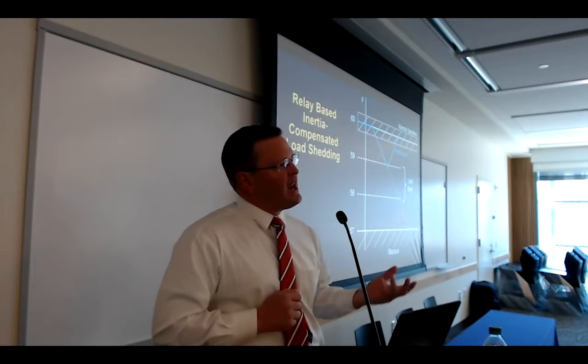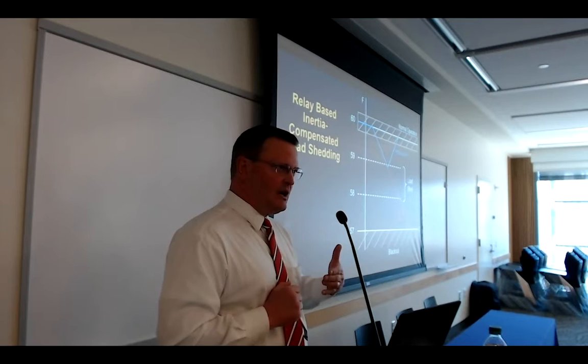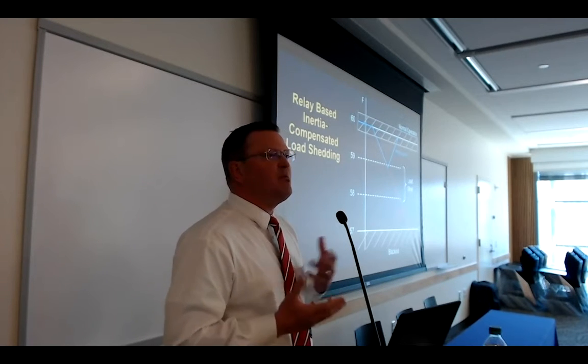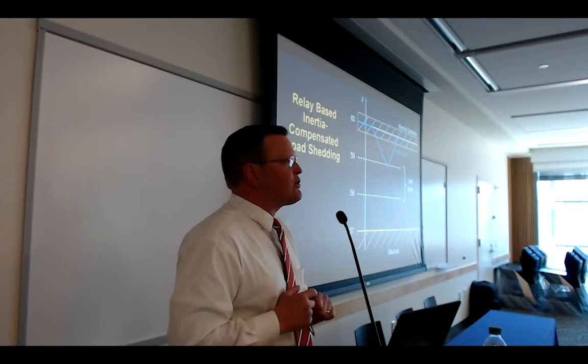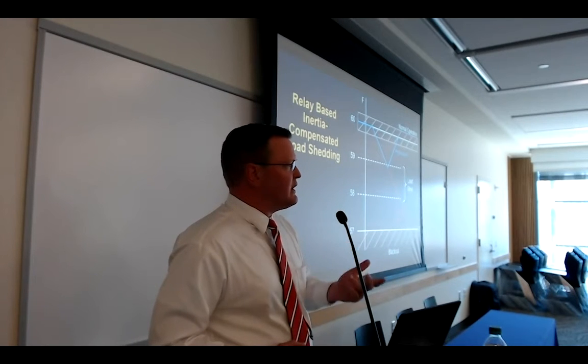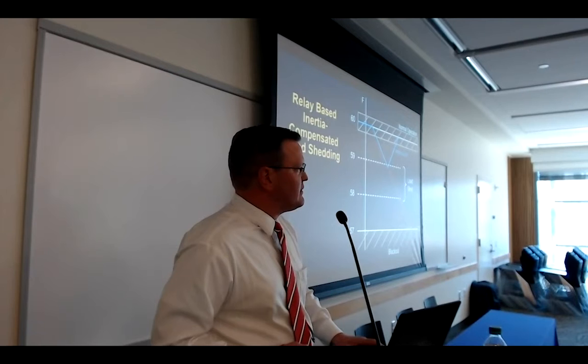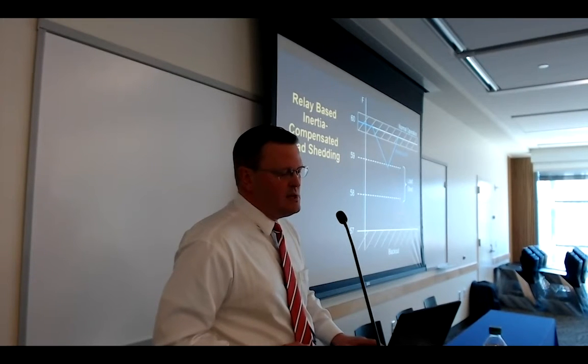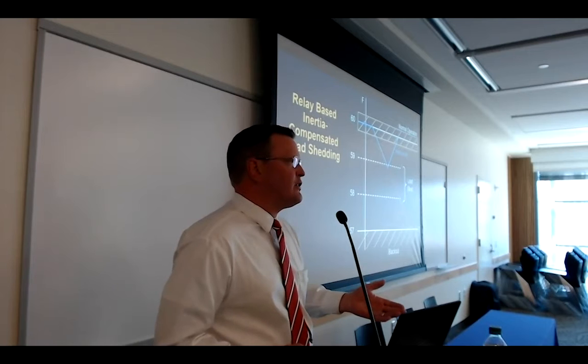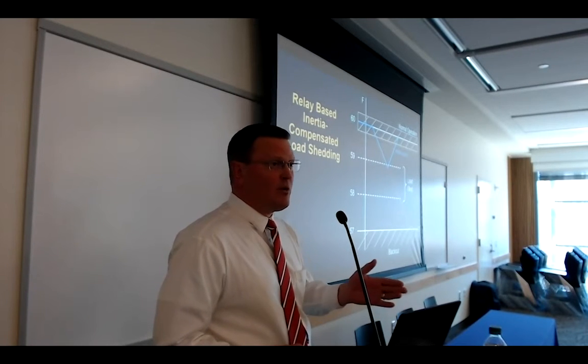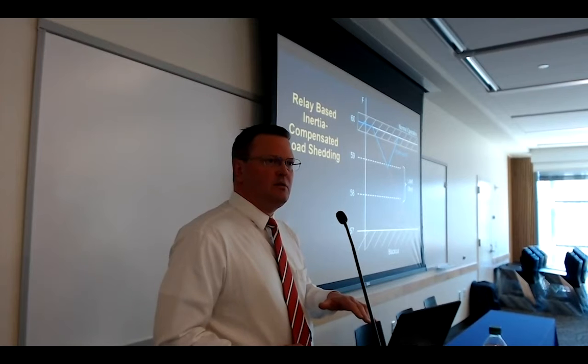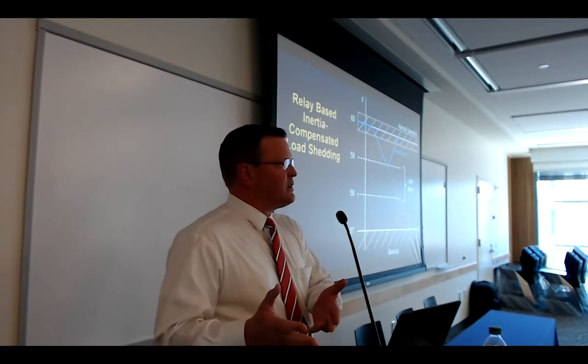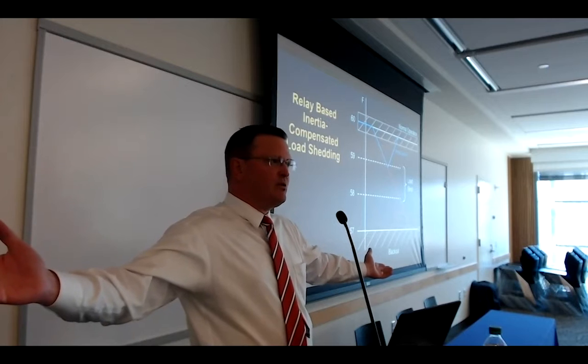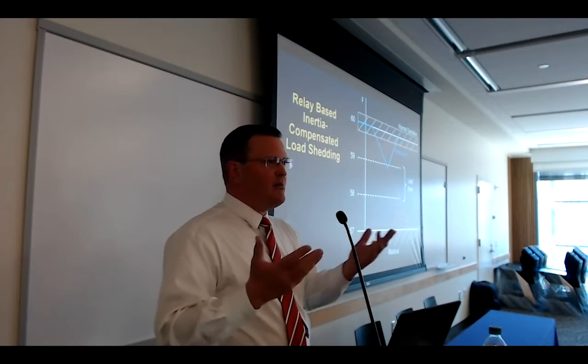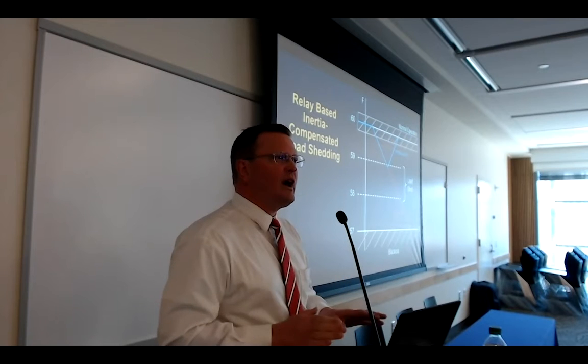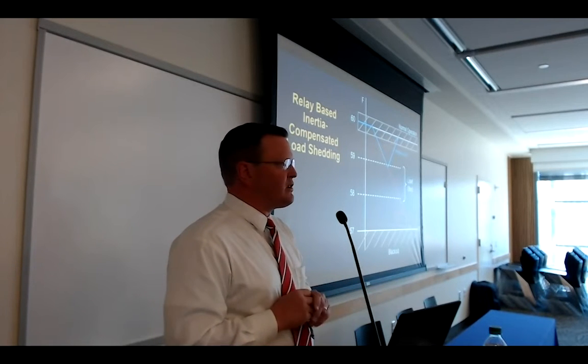The mismatch between mechanical energy, the fuel into the engine, and the electrical energy out is the power mismatch. That's characterized by inertia times the rate of change of frequency, or RPM if it's an engine. So we can take a failing, under-frequency system and always make the right decision. We just tell the relay what the inertia is, what all the relays of the inertia of their respective engines are, and they add themselves up and take care of business. That's how Microgrid 101 works with the protective relay today.